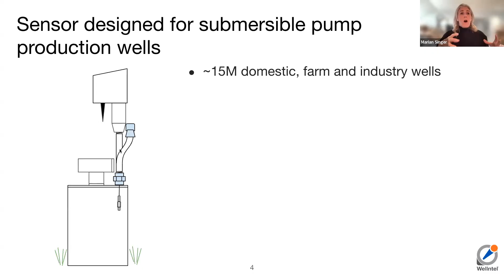Basically how that works: a little sound signal is made here in the sensor, it goes down into the well, bumps up against the water level, and the signal comes back again. All of the information, including reflections off of water pipes and bundles of wire and that sort of stuff, is collected with a microphone that hangs maybe 3 to 4 inches underneath that well seal.